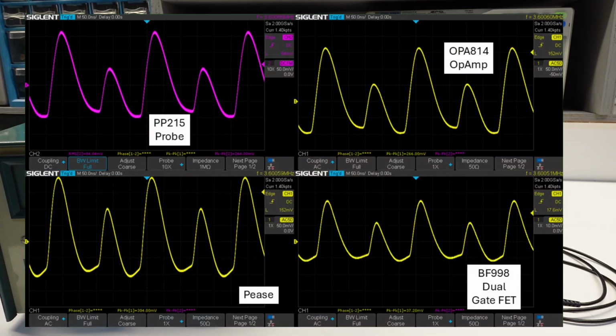There's 4 plots here. The one in the upper left, the purple graph, that's the PP215 probe by itself. Now it looks very much like the signal taken across the entire load, but of course it's at a lot lower voltage, around 264 millivolts peak to peak. And that's compatible with all 3 probes, so now that I know I'm not going to blow up my probes, I proceeded to make the measurement on all 3 of them one at a time, and that's the other 3 graphs shown here in yellow. And of course the scope was set to 50 ohms input impedance for each of these 3 probes.